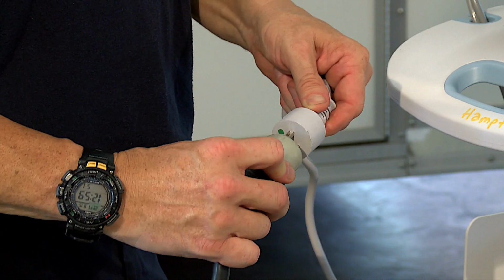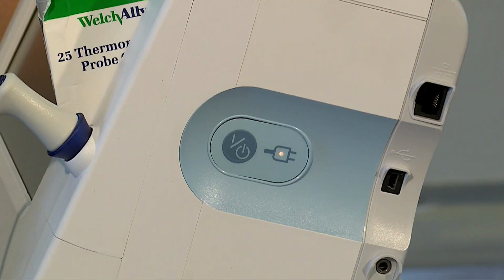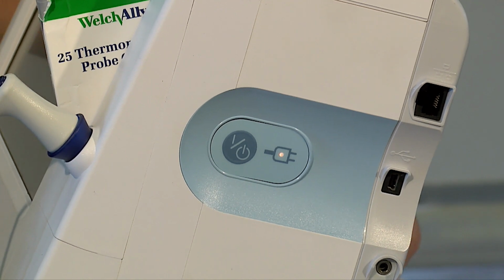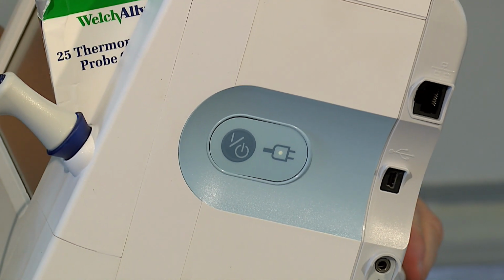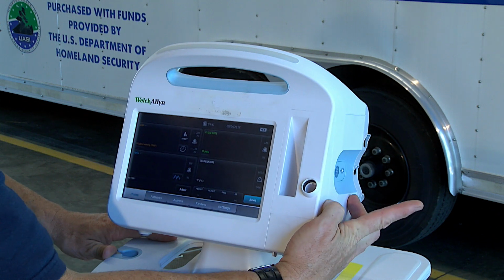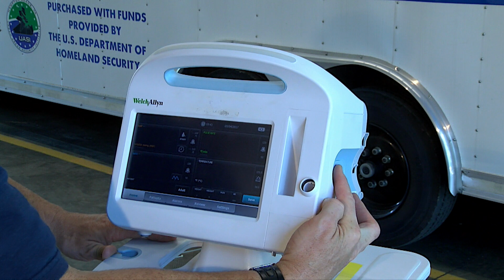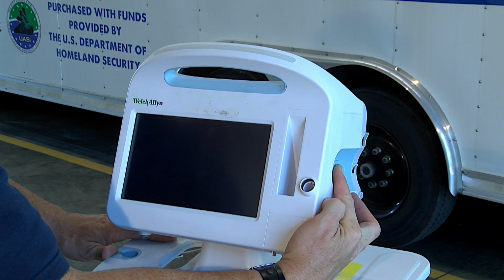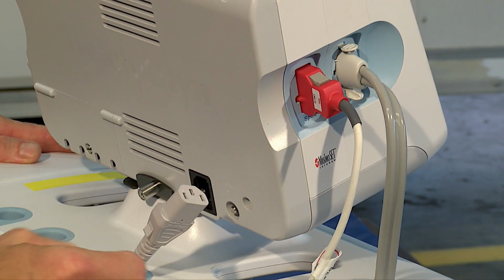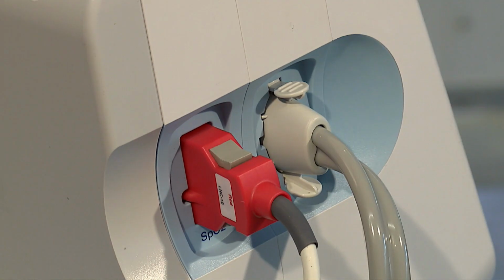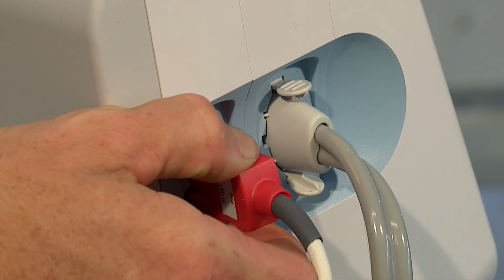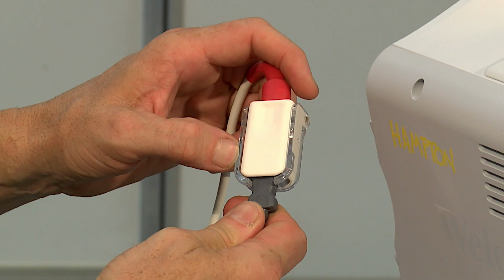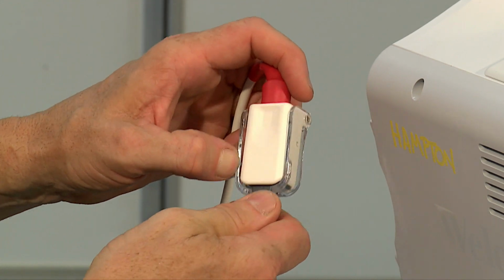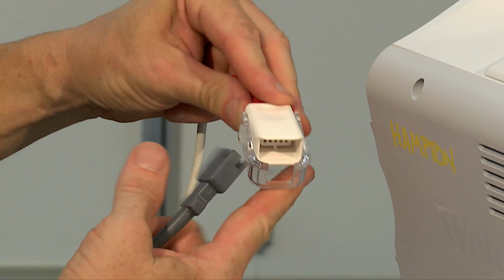Takedown. First, unplug the power cord from the power supply and see that the indicator light next to the monitor's power switch has gone off. Briefly push the power button and the screen should be visible. Next, hold down the power switch until the monitor is fully powered down. Unplug the power cord from the back of the monitor. Then unhook the SPO2 cable by depressing both pins on either side of the connector. Separate the SPO2 cable from the patient cable by lifting up on the clear plastic retainer and separating the cables.